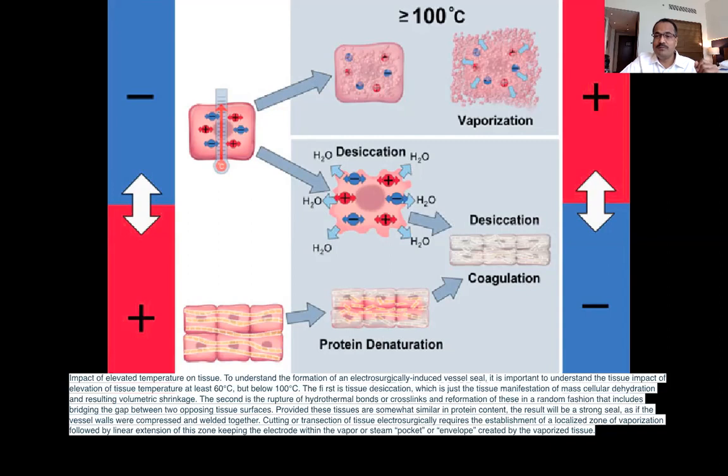So maybe I would consider this the coag current, which is a high voltage. Now one person, instead of receiving one chocolate, is receiving 50 chocolates. So it's a high voltage, but fewer people. Practically, the option for me is to give one to each of the 100 and develop more friends. That is why the cut current is better. I will explain as we go ahead how it is better than the coag current, because the coag current, being a high voltage, may create more energy and lateral thermal damage. We'll see that later.